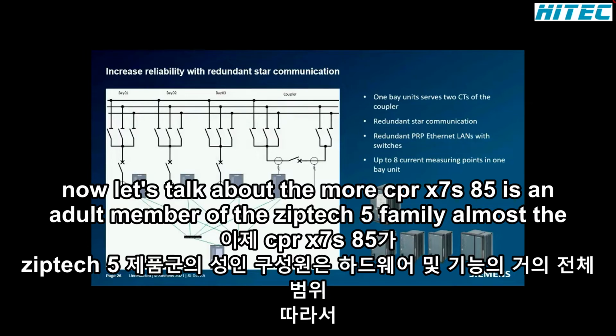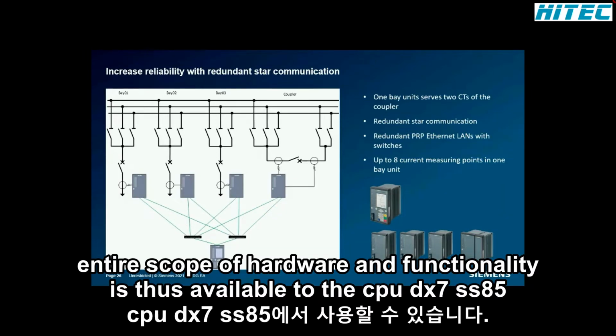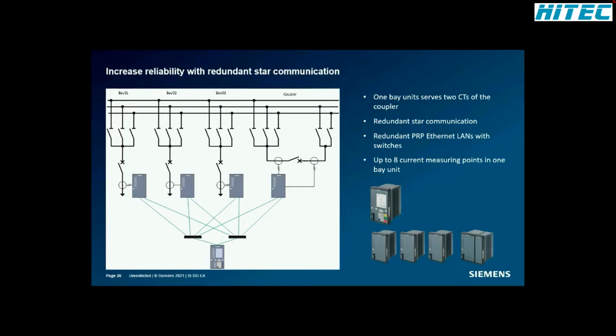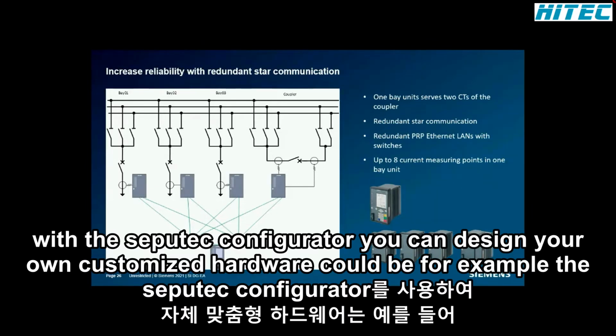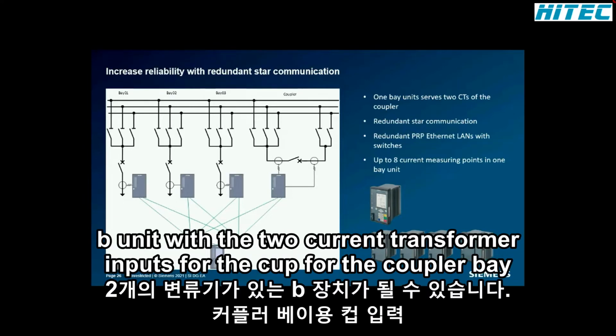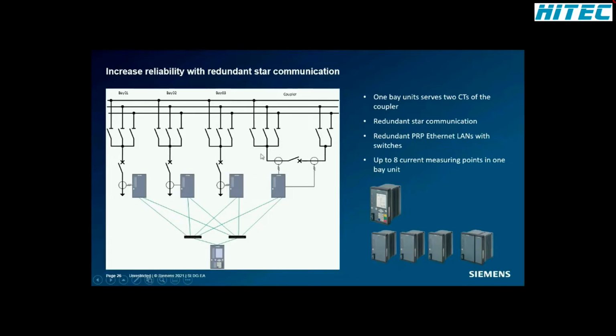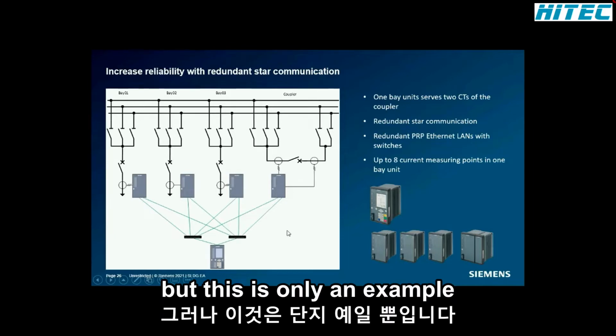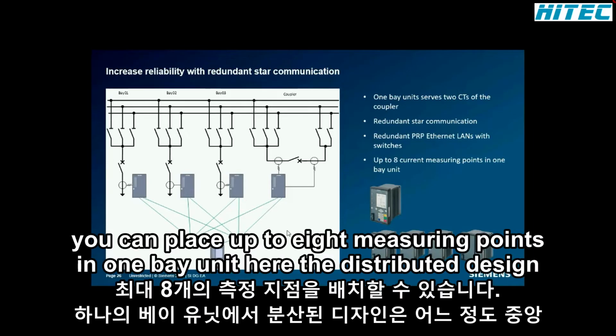SIPROTEC 7SS85 is an adult member of the SIPROTEC 5 family. Almost the entire scope of hardware and functionality is thus available to the SIPROTEC 7SS85. With the SIPROTEC configurator, you can design your own customized hardware. This could be, for example, the bay unit with the 2 current transformer inputs for the coupler bay. But this is only an example. You can place up to 8 measuring points in one bay unit.